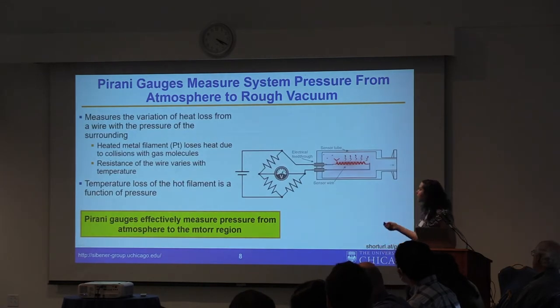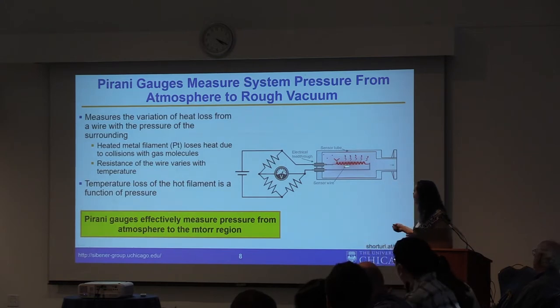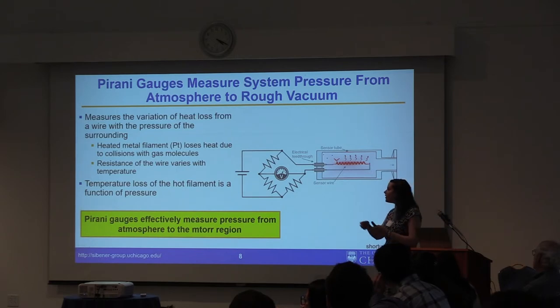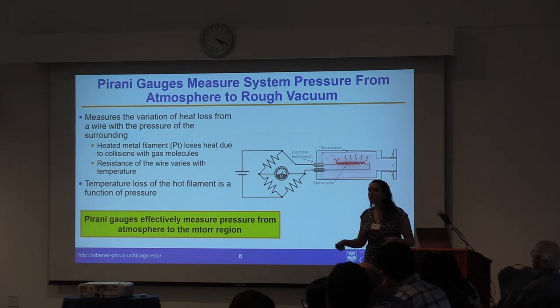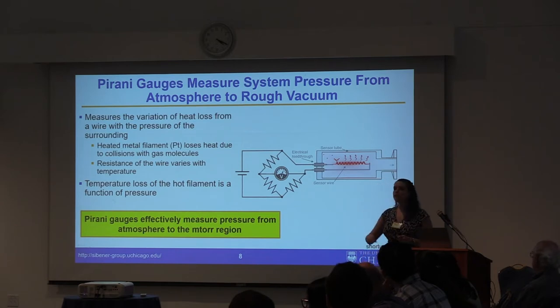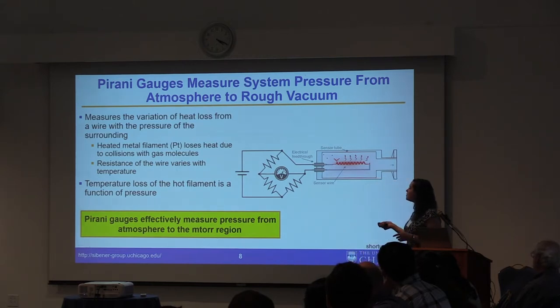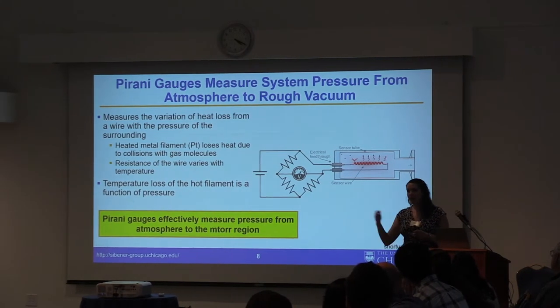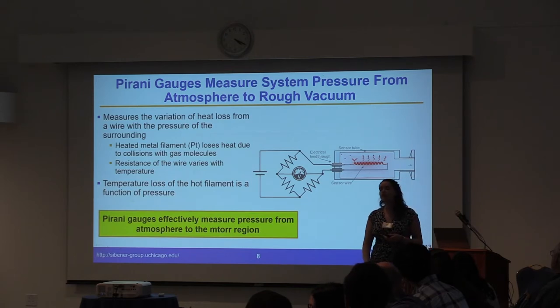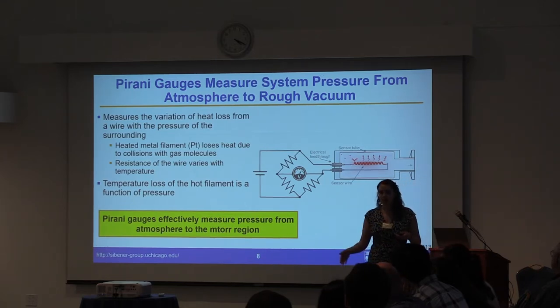The Pirani gauge works by having a metal filament inside. As gas molecules collide against the filament, there is heat loss or heat transfer. They have calibrations where the amount of heat loss equals a certain pressure, because a certain number of molecules will be hitting your filament in that regime. This directly correlates temperature loss to pressure, allowing measurement from atmosphere — where you'll have many collisions and a lot of heat transfer — down to mid or high vacuum where you'll have fewer collisions and less heat loss.